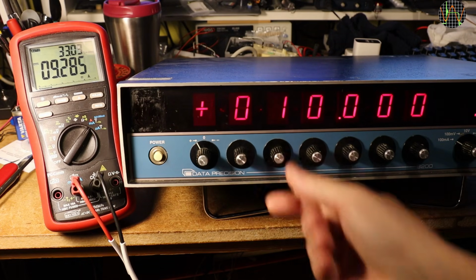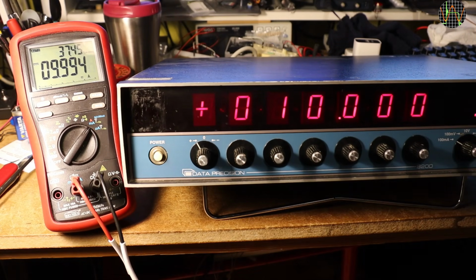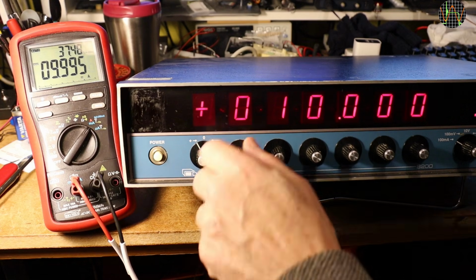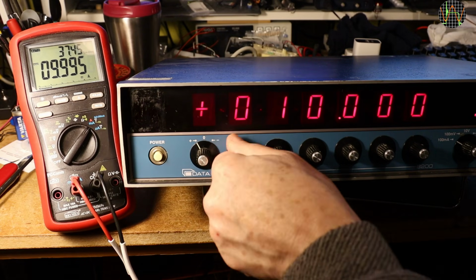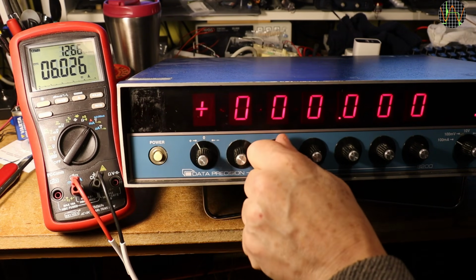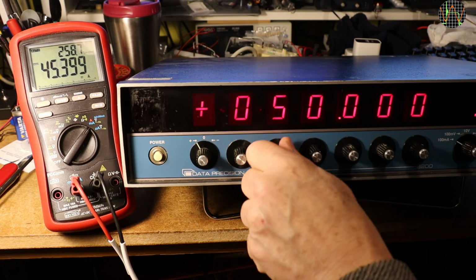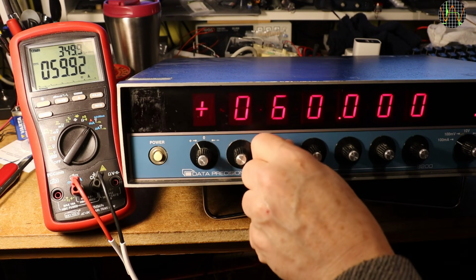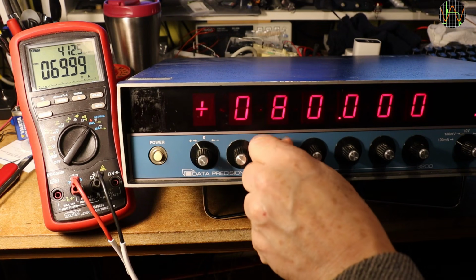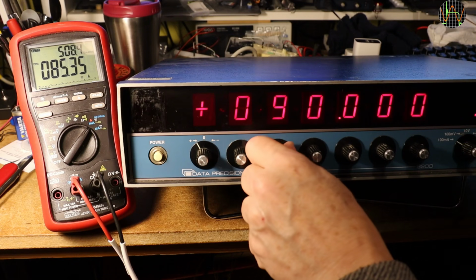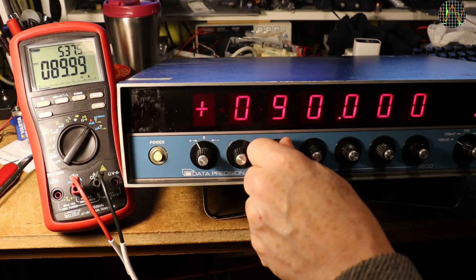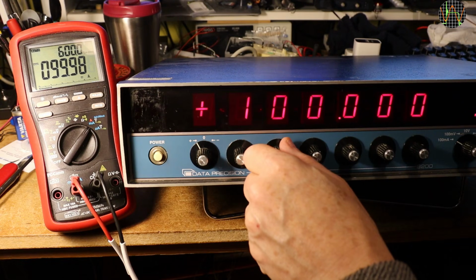Now for the milliamp range. First 10 milliamps. On milliamps, the accuracy of the BM869S is about 10 times less than for volts, so I'm not surprised by the reading. Notice that the 8200 ignores my attempts to set the highest digit. As I mentioned, this is because the current output is limited to 100 milliamp max. By using the 10 milliamp digit, I can of course dial that one up all the way to 100 milliamps.